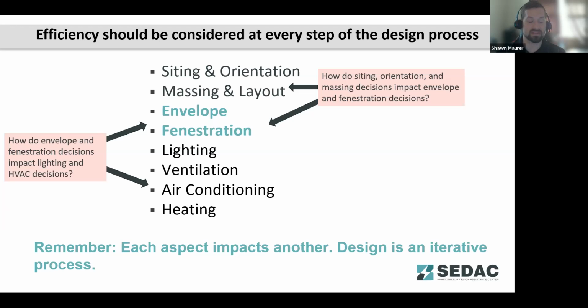It's very expensive to go back and renovate an envelope to add insulation, and difficult to do properly. And so focusing on that first with your initial designs, paying attention to your building siting, orientation and massing, trying to take advantage of even just slight benefits in passive design there, even if it's not a primary focus, improves the resiliency of your building. And then when you focus on the envelope as far as insulation and fenestration improvements, you're decreasing the costs you're going to have later on for sizing of your HVAC systems and ventilation systems. So there's a cost trade-off here with the envelope, where even though there might be some additional cost up front for the envelope design, you can save on those costs on the HVAC and lighting design.